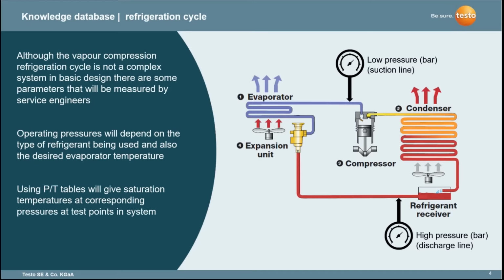So why digital manifolds? Why manifolds just generally? Obviously, here we're talking about devices that are typically used by the refrigeration, air conditioning and heat pump sector. If you've got a little bit of background knowledge, we'll just cover this anyway: we're talking about why we're monitoring the vapor compression cycle in these sorts of systems, to get an understanding of how they're operating from an efficiency and setup point of view. What we're looking at is the operating pressure on the low side and the high side of the system, so either side of the compressor. Depending on these pressures and the refrigerant used, we can then use pressure and temperature tables to give us the corresponding saturation temperatures within the evaporator and condenser. So primarily, this is what an analog gauge set is always doing. It's looking at these pressures and then having to either cross-read over the dials or use a pressure and temperature table to get the temperatures.